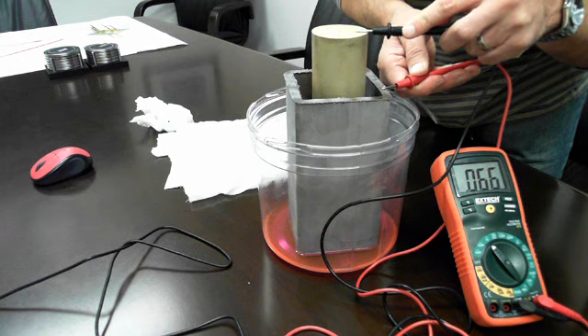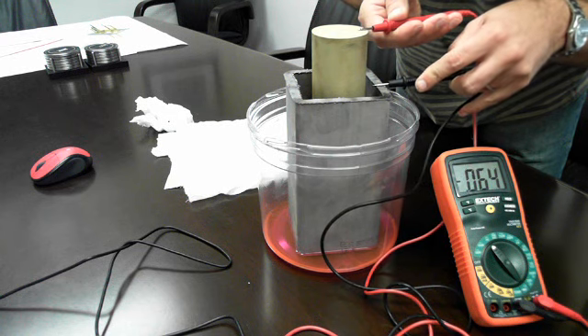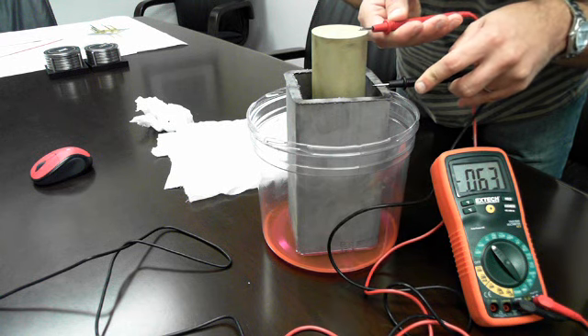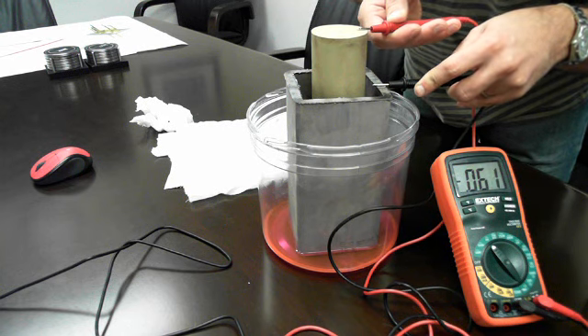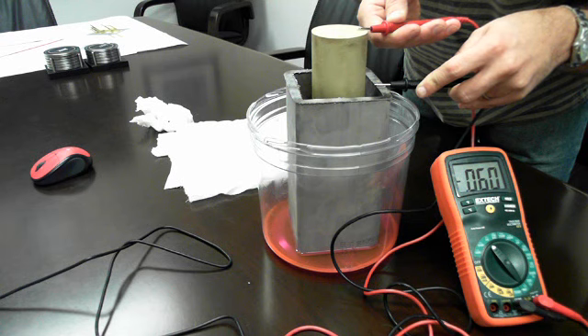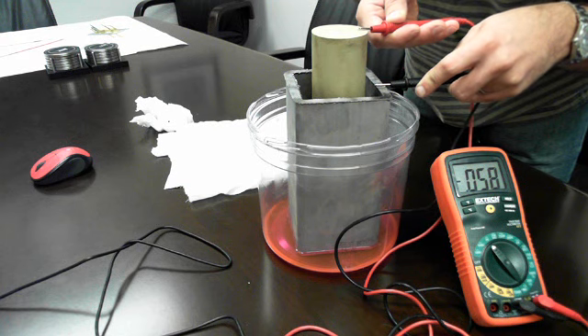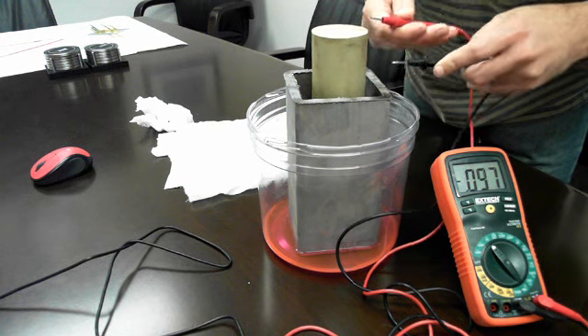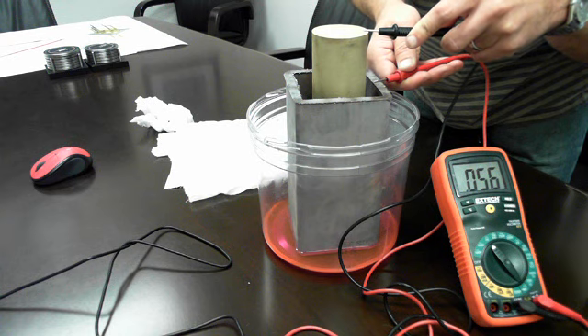So the dissimilar materials between carbon steel and bronze on a cylinder with water-based glycol Houghto-Safe 273 does in fact create a battery effect and has voltage across components. There you have it.